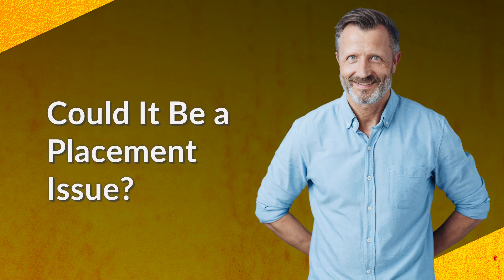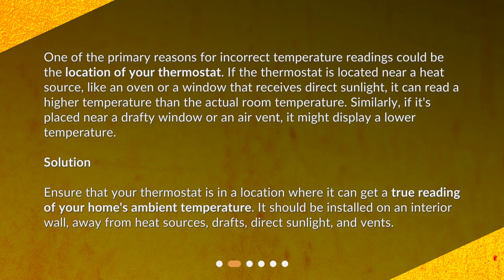Could it be a placement issue? One of the primary reasons for incorrect temperature readings could be the location of your thermostat. If the thermostat is located near a heat source, like an oven or a window that receives direct sunlight, it can read a higher temperature than the actual room temperature. Similarly, if it's placed near a drafty window or an air vent, it might display a lower temperature. Solution: ensure that your thermostat is in a location where it can get a true reading of your home's ambient temperature. It should be installed on an interior wall, away from heat sources, drafts, direct sunlight, and vents.